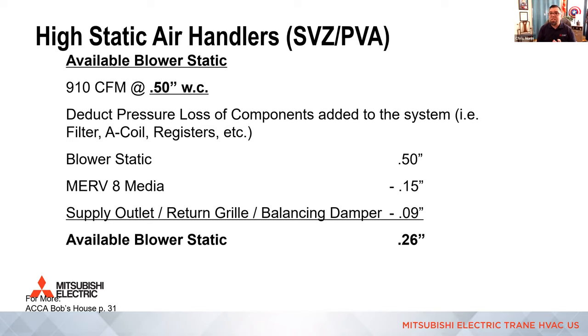So Steve asks, so the ECM process variable is pressure, not flow? Just to be sure, Steve, yes. ECMs can control based on volume of air, but they have a maximum static pressure setting they can't overcome. If you didn't control maximum static, the motor would continue to ramp up on a poorly designed system and the control board of the motor would fail. So most ECM motors in the last 15 years have a maximum external static pressure as well.